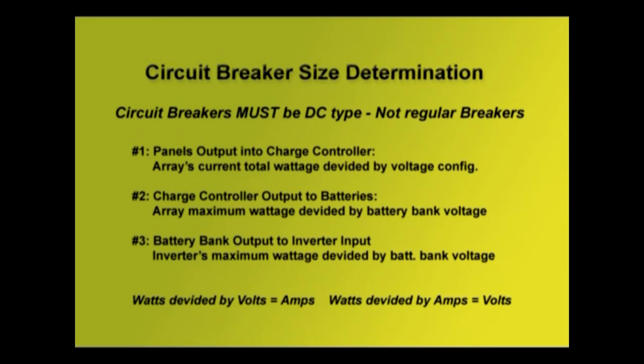Plus, all of these inverters have a little bit of surge capacity, so momentarily, instantaneously, a larger amount of current may be drawn. That's why it needs the full 1.5 amount, and you may be able to go a hair over that, and these large breakers tend to come in 150, 175 amp sizes. Again, all these 3 breakers can go into the same box. They're just going to be wired separately.